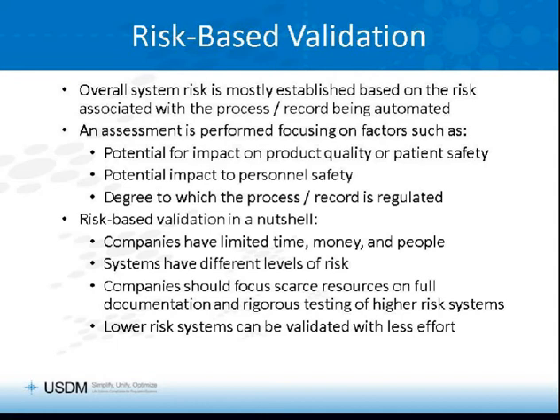Same thing applies to computerized systems used to manufacture the product. As you back away from the product into, say, automated systems that manage your change control or your investigations or deviations, these could have an impact on product-related activities, but it would be an indirect impact. Those systems start to sound more like medium-risk computerized systems. If you've got a system that keeps track of and manages your training records, those are still regulated records, but you might even call that a low-risk system.